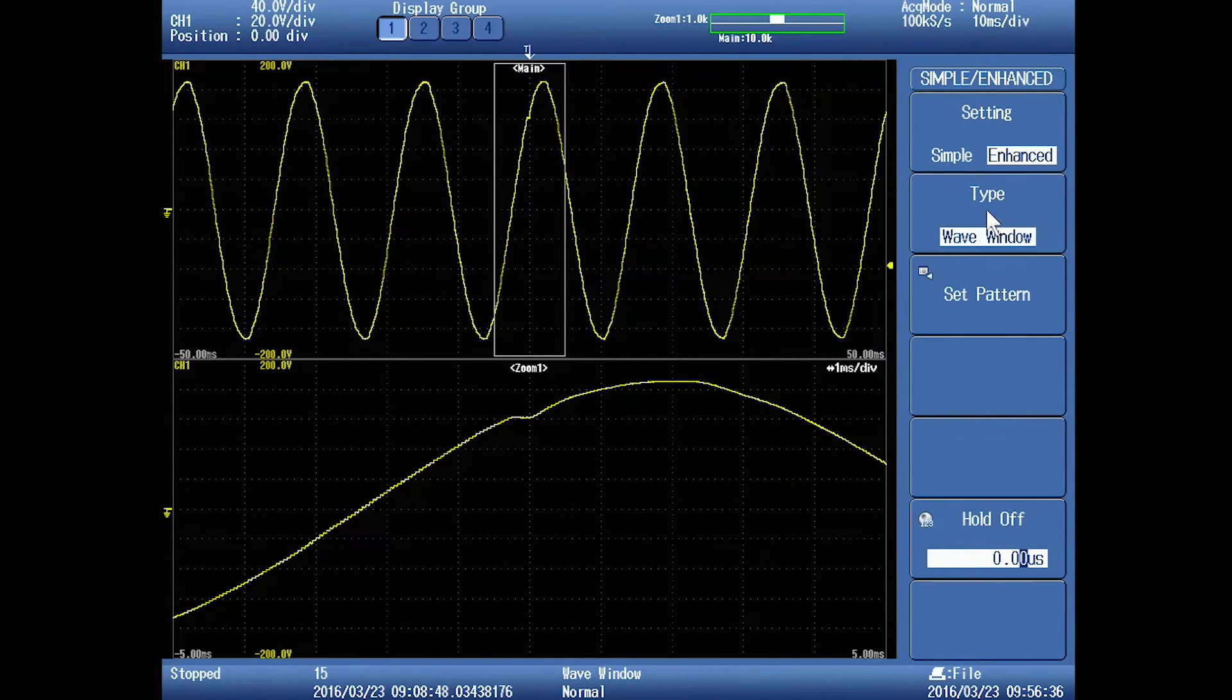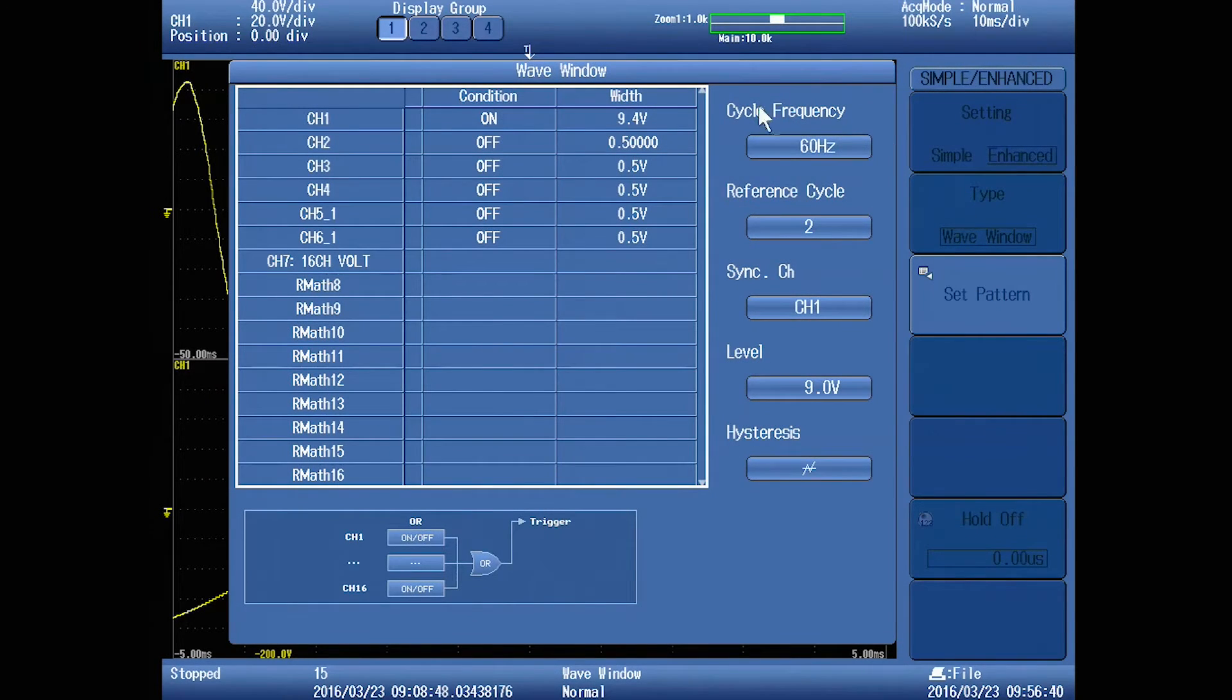You're going to set type as wave window, and under pattern there are several settings. One is to tell it which channel to watch, that's channel one in this case. You're going to give it what's called width. If this were nine volts exactly, it would tolerate plus and minus four and a half volts of voltage around your nominal sine wave.